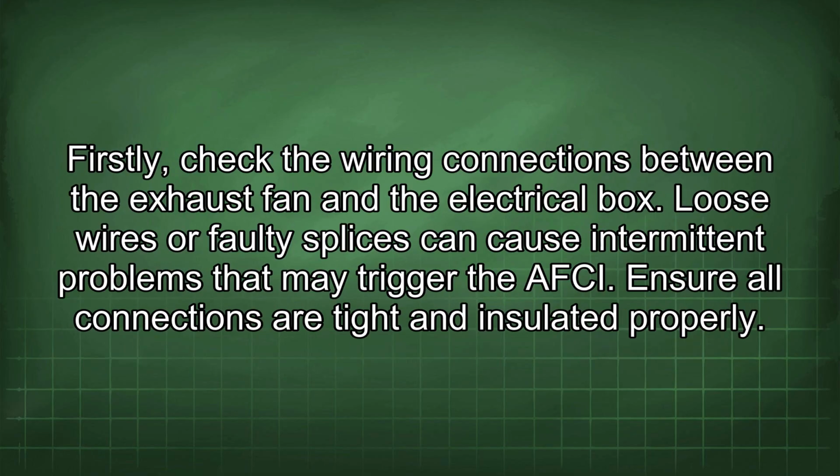Firstly, check the wiring connections between the exhaust fan and the electrical box. Loose wires or faulty splices can cause intermittent problems that may trigger the AFCI. Ensure all connections are tight and insulated properly.